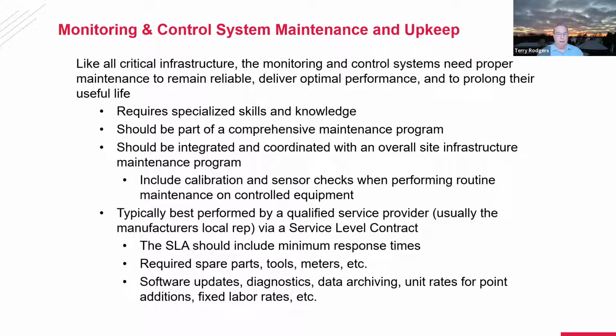Again, it's best to have a service level contract if you don't have the in-house expertise to do this. When you develop a service level contract with a building management service provider, a controls vendor, there's certain things you want to include in that service level contract. The obvious one is the minimum response times. I have an anomaly. You have 15 minutes to call in and tell us what to do, and then you have 1 hour to get on site.